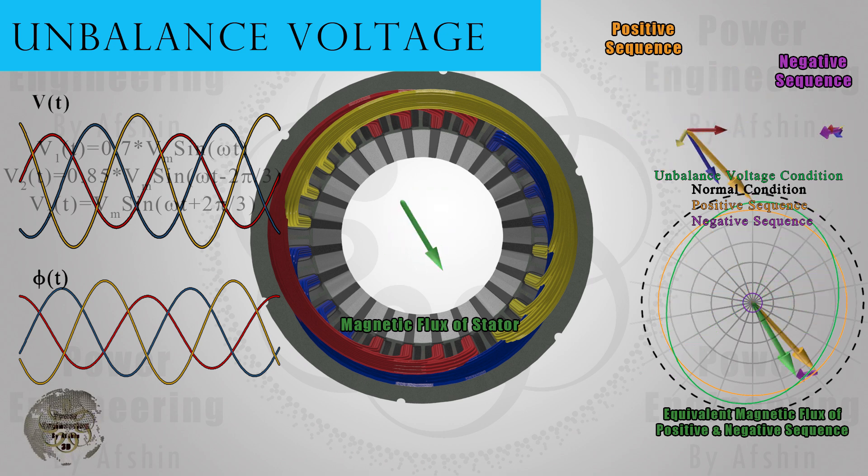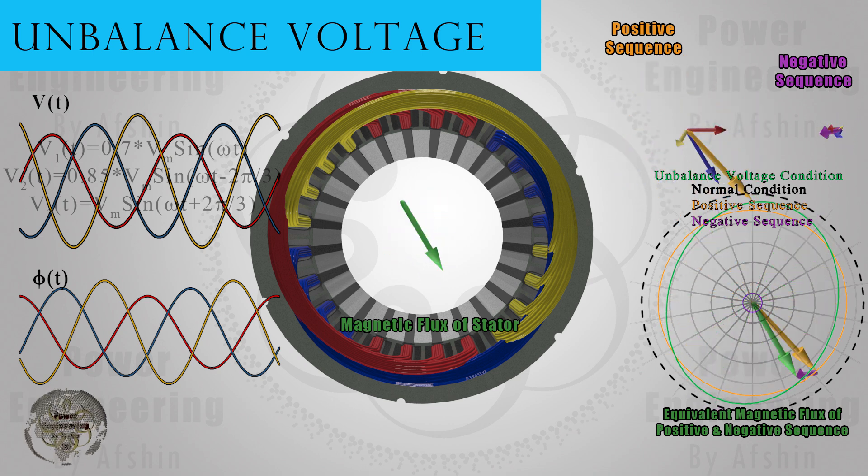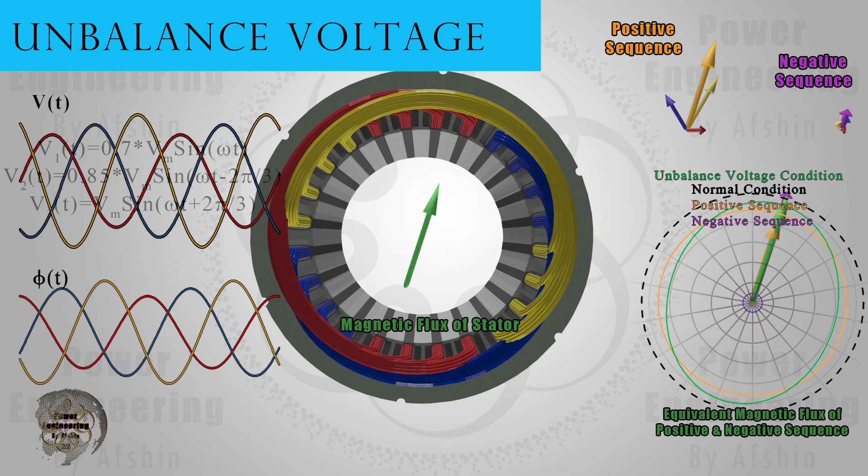Additionally, the negative sequence leads to more heat generation and losses. On the left side, you can observe voltage and magnetic flux curves, showing the magnitude of the magnetic field at 360 degrees. Also, on the right side, you can observe the size and rotation direction of the positive and negative sequences and their sum. The sum of the positive and negative sequences equals the magnetic flux inside the stator.